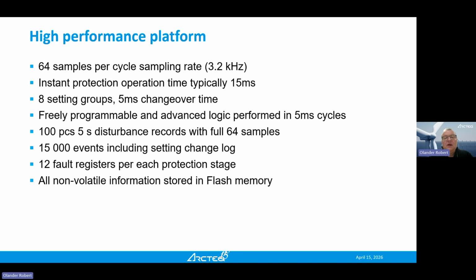And then I think if you have ever looked at our AQtivate, which is our setting and configuration software, there's a lot pre-configured so that you just activate it and take it into use and do the setting. But then if this is not enough or this is not according to what you need, then we have a full logic, freely programmable full logic with all the functions that a logic system provides, and it's very fast. It's performed in 5 millisecond cycles, and also I would say that it's unlimited. You can build up how big a logic system you need. You can add the logic functionality there, so basically unlimited.